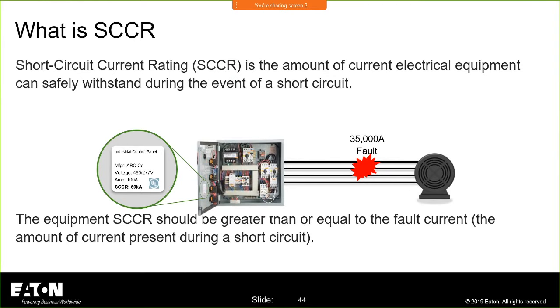Now, just to talk a little bit about the short circuit current rating. A short circuit current rating is the ability of this product that you're seeing to withstand the current passing through it. So if I have a source and a fault downstream, all of this equipment has to deliver that fault current. Anything that is in the current carrying path has to hold together under the magnetic forces until the overcurrent device up above clears that fault. That's an important thing to remember: the short circuit current rating is not stopping the flow of current.